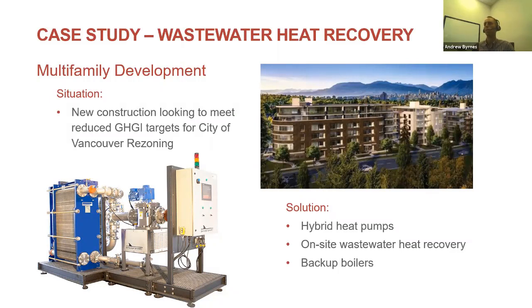This was a project built about 4 or 5 years ago, a 160 unit multifamily development on Cambie Street in Vancouver. It needed to achieve a greenhouse gas intensity target to comply with City of Vancouver rezoning policies, so the solution was on-site waste heat recovery. The building required a sump pump or wet well for collecting sanitary flows before ejecting them into the city sewer system, which provided a great opportunity to do heat recovery from the sewage in that holding tank.